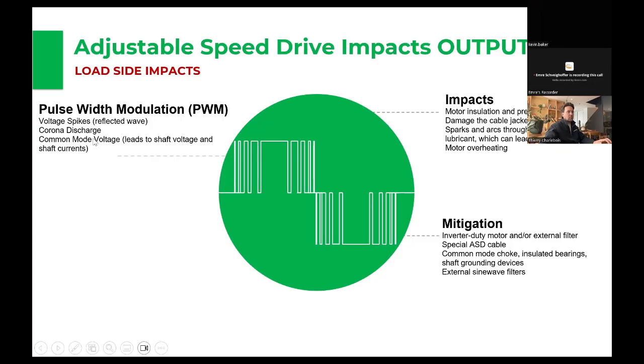You also have leftover energy that's common to all three phases and to ground, and that's the common mode voltage. And that starts to show up in discharges in the bearings of the motor, what we call shaft currents or bearing currents. And then you have to put insulation on your bearings and so on. So what you end up doing is paying more for the insulation of your motor, the insulation on your VFD cable, anything on the bearing has to be insulated, and then the shaft ground has to be introduced. You have to watch out what kind of lubricants you're using, because they could be conductive over time. They can break down, and so on and so forth. So this really shortens the motor life and can shorten the cable life, and there could be some catastrophic failures as well.